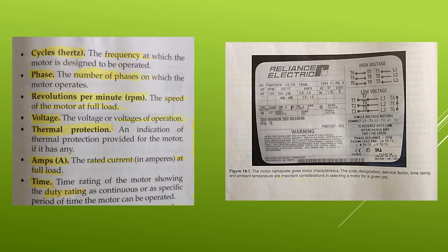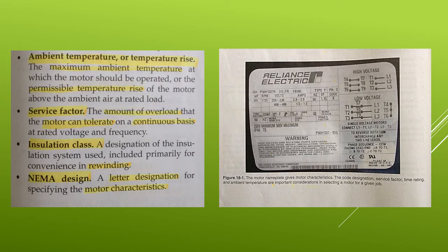The time, which is the time rating of the motor, showing the duty rating as continuous or as a specific period of time the motor can be operated. Ambient temperature or temperature rise is the maximum ambient temperature at which the motor should be operated, or the permissible temperature rise of the motor above the ambient air at rated load. The service factor, the amount of overload that the motor can tolerate on a continuous basis at rated voltage and frequency. Insulation class, a designation of the insulation system used, included primarily for convenience in rewinding. And finally, the NEMA design, the letter designation for specifying the motor characteristics.